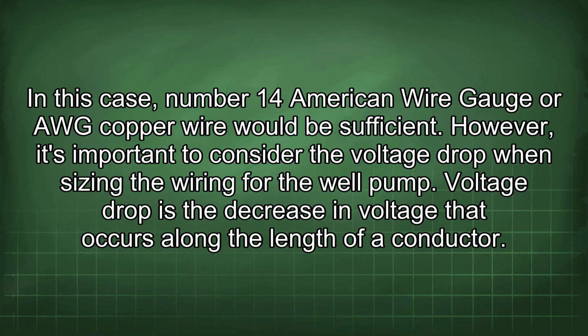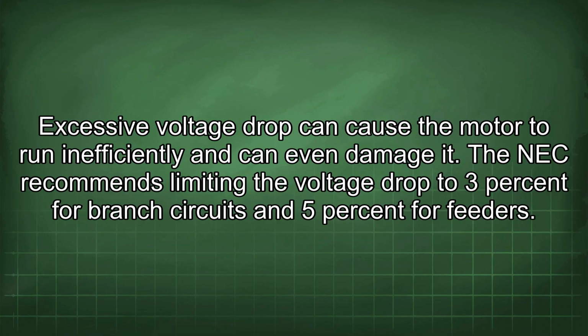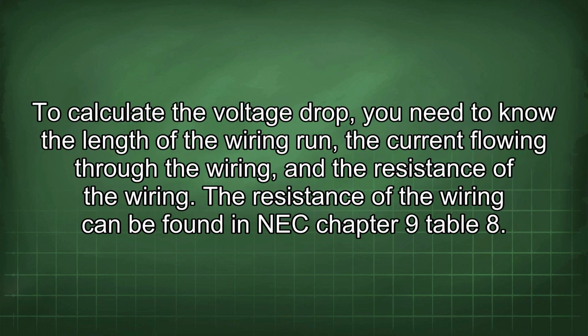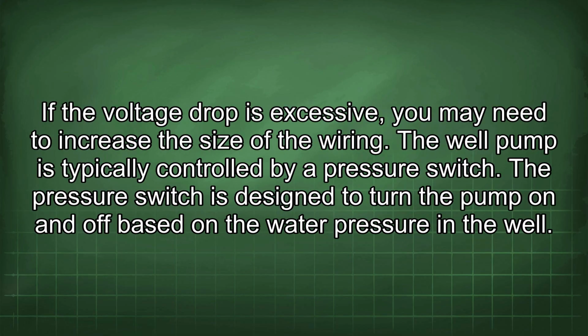However, it's important to consider the voltage drop when sizing the wiring for the well pump. Voltage drop is the decrease in voltage that occurs along the length of a conductor. Excessive voltage drop can cause the motor to run inefficiently and can even damage it. The NEC recommends limiting the voltage drop to 3% for branch circuits and 5% for feeders. To calculate the voltage drop, you need to know the length of the wiring run, the current flowing through the wiring, and the resistance of the wiring. The resistance of the wiring can be found in NEC Chapter 9, Table 8. If the voltage drop is excessive, you may need to increase the size of the wiring.